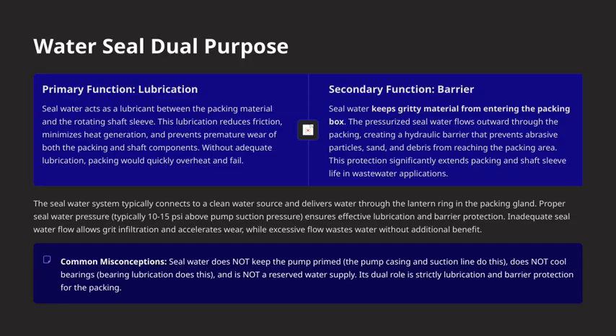Now, let's take a closer look at the dual purpose of the water seal. First, its primary function is lubrication. The seal water acts as a lubricant between the packing material and the rotating shaft sleeve. This is crucial because it helps to reduce friction, which in turn minimizes heat generation. Without this lubrication, both the packing and the shaft components could overheat and fail prematurely. So proper lubrication is essential for the longevity and reliability of the pump.